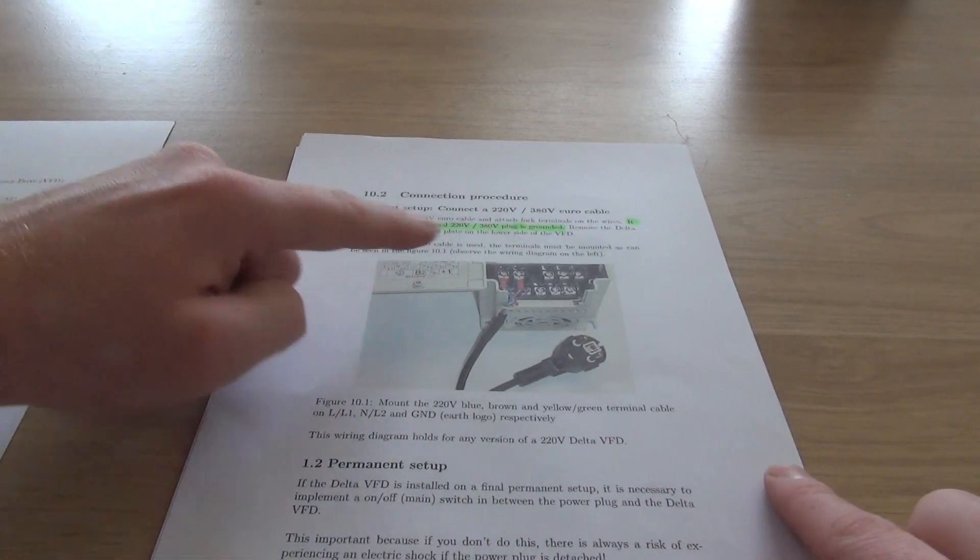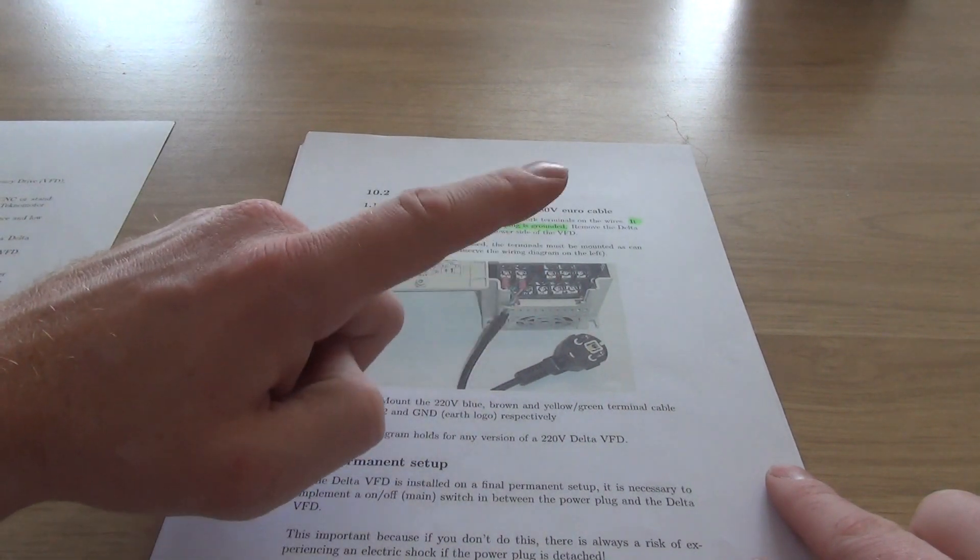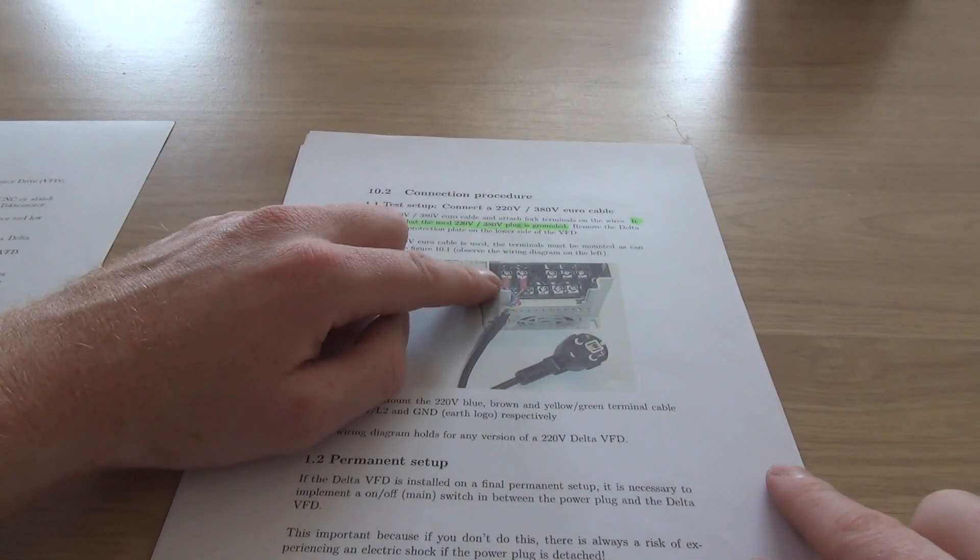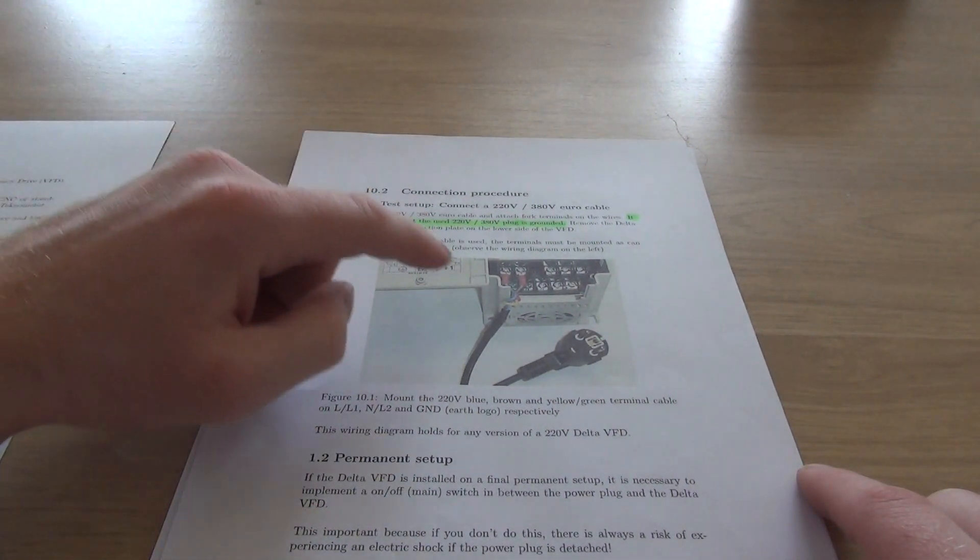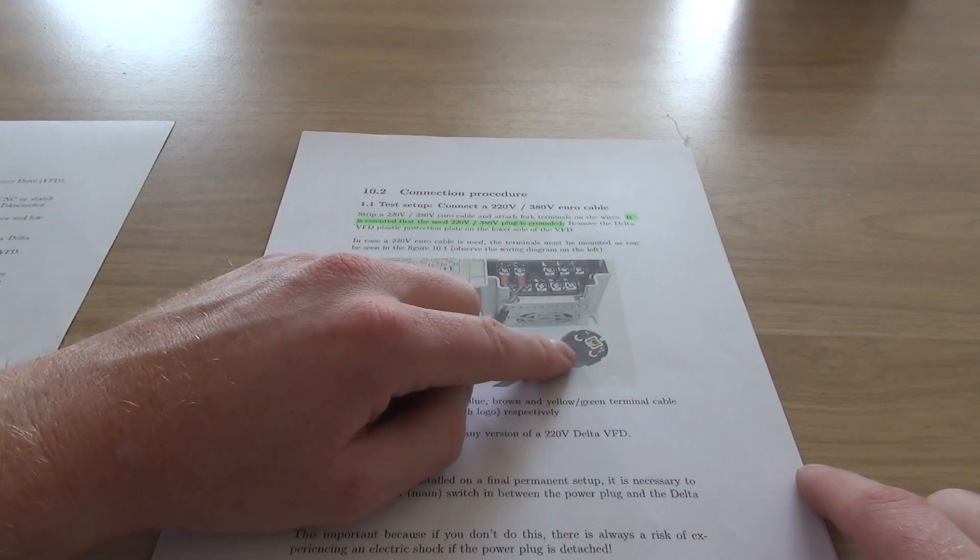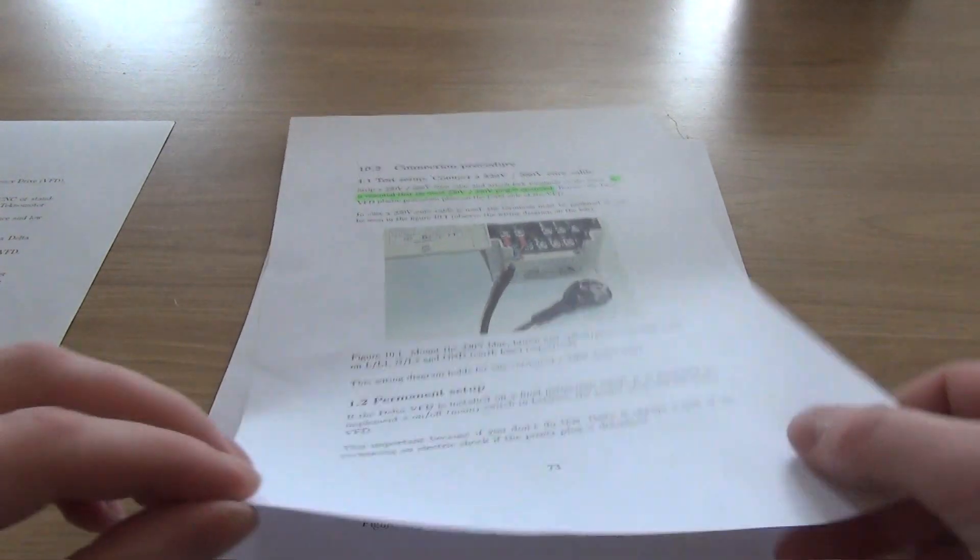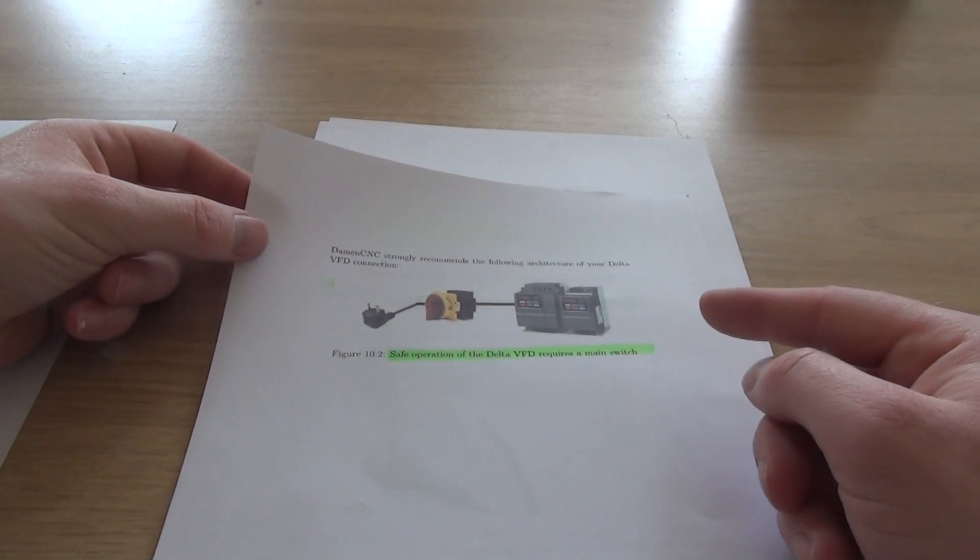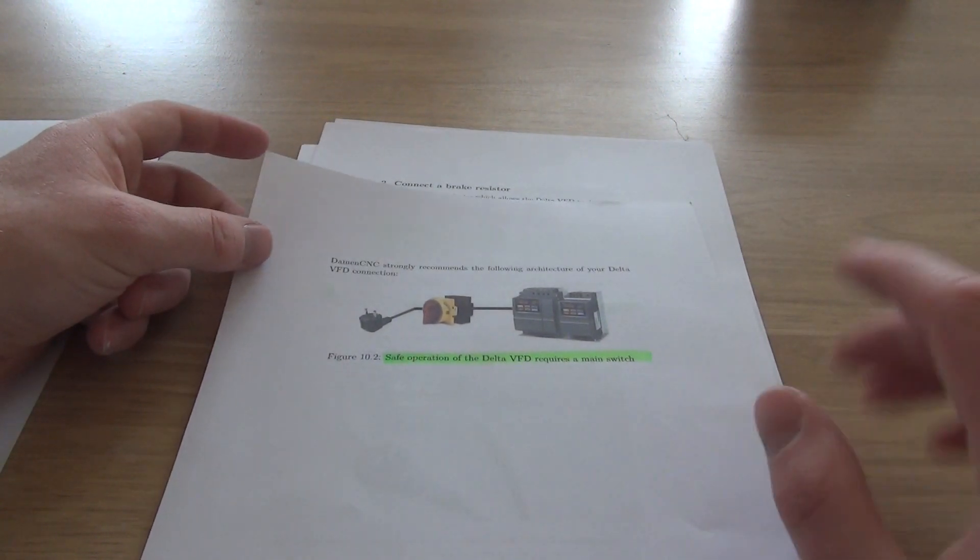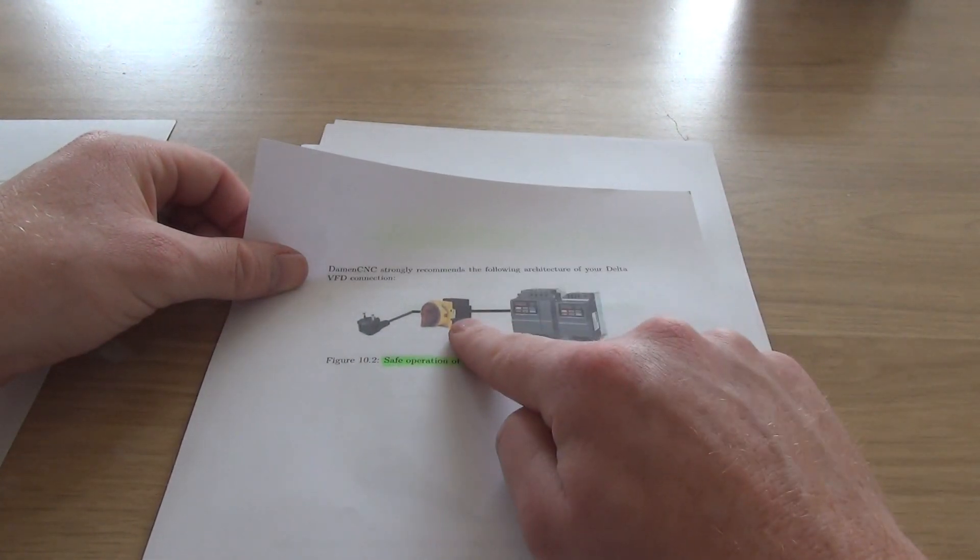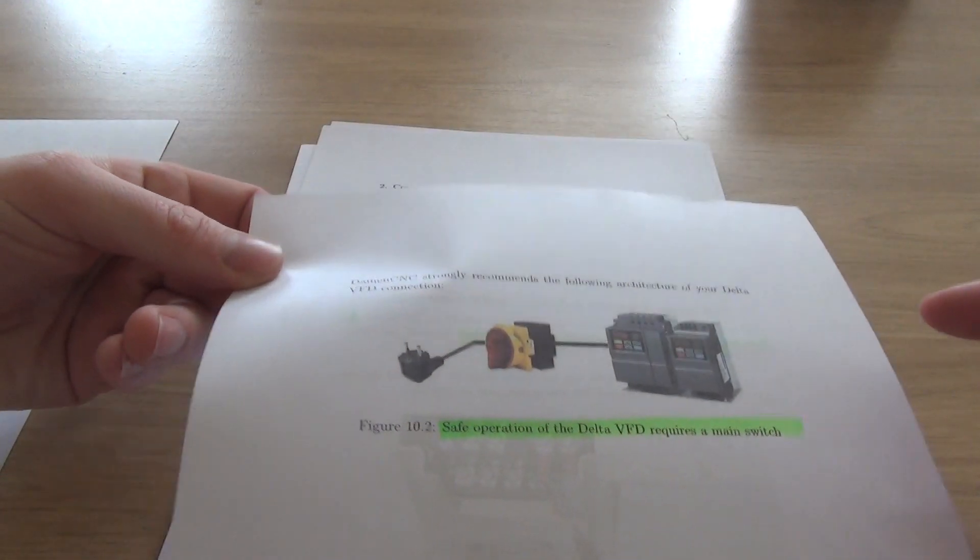Second thing to take note of is only use a grounded plug with a grounded wire, so no two wire connections. I'm using the 220 or 230 volt single phase unit, so I have three wires, one ground with the grounded Euro connector. I'm gonna power it by just using a plug for now because I'm just testing it and setting up the VFD. But if you're gonna use it in a permanent setup, always make sure to use a switch.